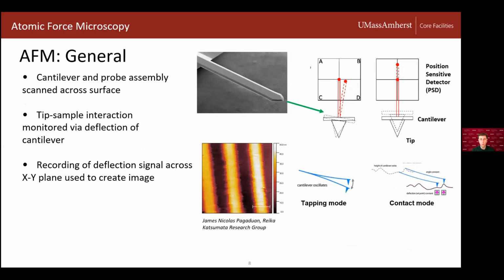And just very quickly, to give you an idea of what AFM is or how it works: the general principle in AFM is that we have a rectangular cantilever in which a probe is attached to the end of it. This cantilever probe assembly is then moved across the surface of your sample. Depending upon whether your probe is in contact with your sample or not, a lot of different things can happen, right? But essentially there's some interaction between the cantilever probe assembly and the surface of your sample, and this interaction is typically recorded and viewed in terms of a cantilever deflection.